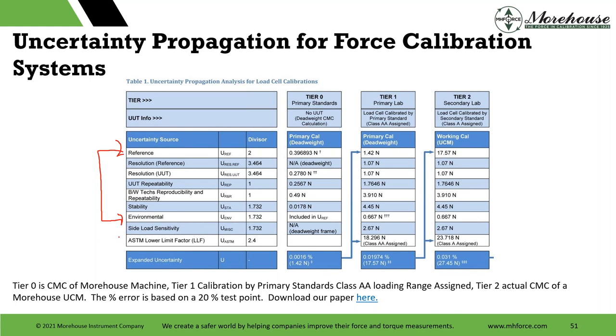And typically for most labs, we recommend using reference standards that operate to the ASTM E74 standard. That gives you a legal standard to fall back on. They call it a lower limit factor with a statistical estimate of errors. That's found in section 8 for those that want to look at E74. And we just did this paper back in 2017, and I still like it because it talks about tier zero.